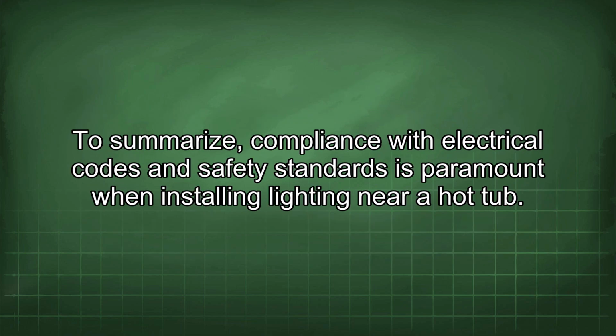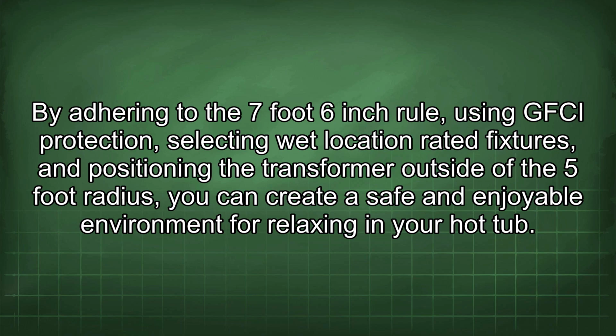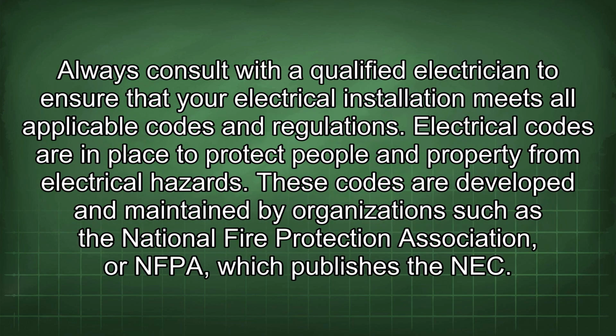To summarize, compliance with the electrical codes and safety standards is paramount when installing lighting in your hot tub. By adhering to the 7-foot 6-inch rule, using GFCI protection, selecting wet location rated fixtures, and positioning the transformer outside of the 5-foot radius, you can create a safe and enjoyable environment for relaxing in your hot tub. Always consult with a qualified electrician to ensure that your electrical installation meets all applicable codes and regulations.